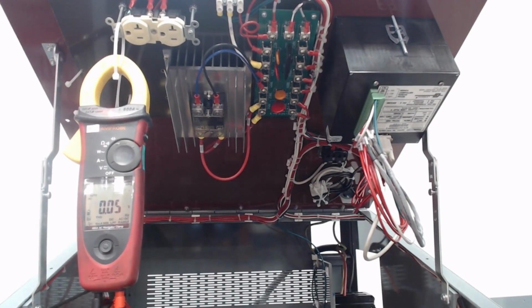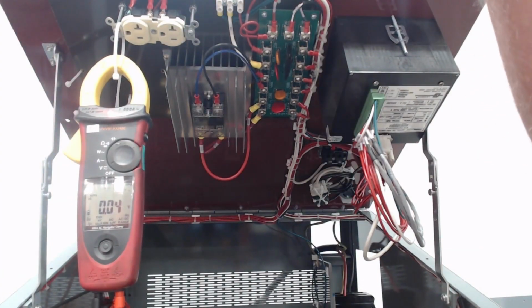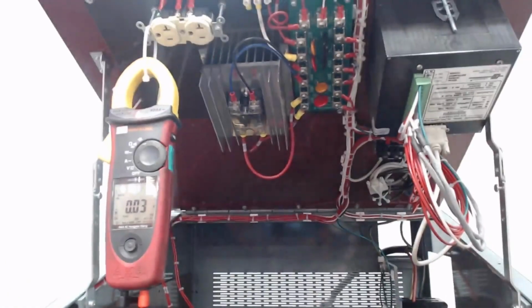Okay, sorry about that. All right, so we've checked that. So at this point, we know that SSR is good because it's allowing it up. You should go ahead and max it out to make sure you get that full 120. If you don't, that DC supply that I was pointing to does have a low and high feature. You can change that tap to account for if maybe instead of 120, you're only getting 110. Or maybe instead of 120, you're getting 130.